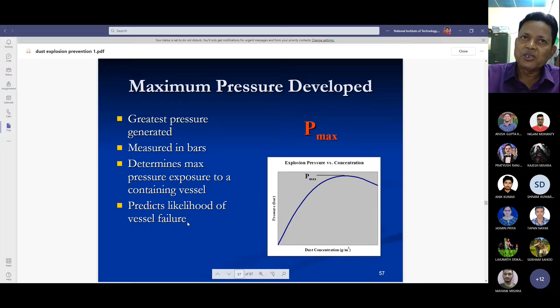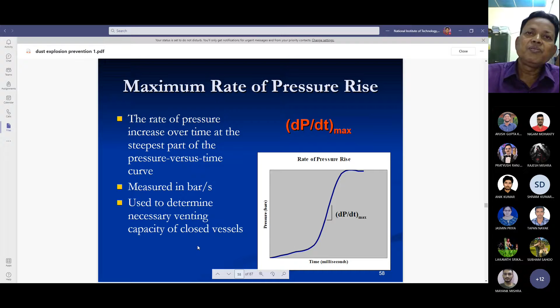So then another characteristic is the maximum rate of pressure rise. This is the pressure, this side is time in milliseconds. The rate of pressure increase over time at the steepest part of the pressure versus time curve is called maximum rate of pressure rise, measured in bar per second, used to determine necessary venting capacity of closed vessels.